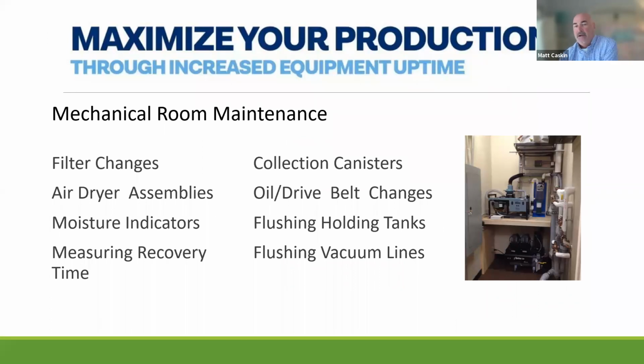Okay, so some things to consider when you're looking at your mechanical room maintenance. Filter changes. Most of your air compressors now are oilless, but they do have air filters that require changing. There are dryer assemblies that dry your air that goes into your delivery units, so your handpieces and syringes and so on and so forth. So those need to be changed out periodically. There are moisture indicators on the equipment itself, on the air compressors, so that you can monitor how dry your air is. We like to measure recovery time, and that's very revealing for a service technician. You want to be able to measure that recovery time.